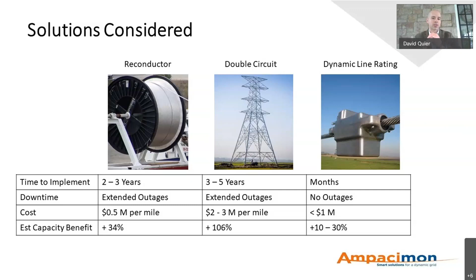Going into our ratings methodology: static line ratings, how we normally establish our line ratings, are very conservative. Especially for normal ratings, we assume zero wind speed and the worst ambient temperature, only toggling for certain seasons, because we have to make sure the lines never burn down. So we always assume worst case, the lowest rating, which prevents us from optimizing our system as much as we'd like. Dynamic line ratings basically eliminate those assumptions.